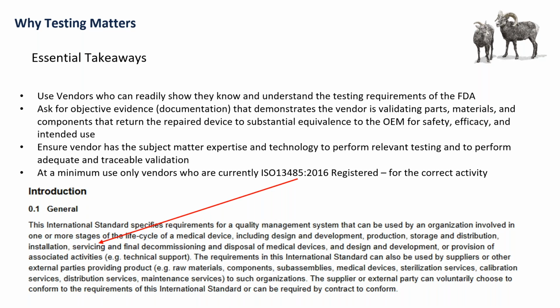Okay? Ask for objective evidence. You should have the ability to ask for objective evidence, documentation that demonstrates the vendor is validating parts, materials, and components that it's using, that return the repaired device to substantial equivalence to the OEM. Okay? And for safety, efficacy, and make sure that they haven't messed with the intended use of the product by leaving something off. Okay? It's a case of the biopsy that we're talking about. So ensure also the vendor has the subject matter expertise and technology to perform relevant testing and to perform adequate and traceable validation. They should have all this.